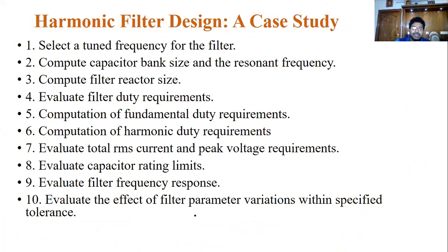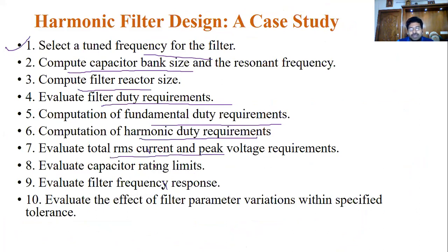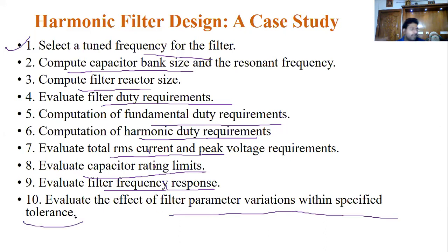Okay, these are the 10 points to design a filter. Select the tuned frequency of the filter. Compute the capacitor bank size. Then the filter reactor size. Then filter duty requirements: the fundamental duty requirements, the harmonic duty requirements, then total RMS current, nothing but peak value, then RMS value, capacitor ratings, then filter frequency ratings, as well as filter parameter variations with tolerance. These are the 10 points. You can keep them in mind to design any type of filter.